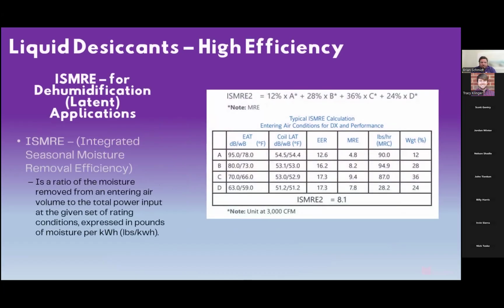Really quick, before we look at the psychrometric chart, I want to talk about ISMRE. For those that are unaware, MRE is moisture removal efficiency. ISMRE is very similar to, sorry, I'm completely blanking. Anyway, ISMRE is integrated seasonal moisture removal efficiency. IEER is what I was trying to compare it to. I apologize. So this is a ratio of the moisture removed from entering air volume to the total power input at the given set of rating conditions, expressed in pounds of moisture per kilowatt hour.